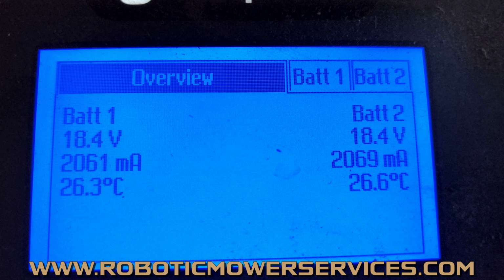That is not completely correct, because if you look at this right here, obviously we're working with a 450 because we got battery 1, battery 2. We got a charge current coming into both the batteries. We have 18.4 volts coming in to both batteries. So we have good voltage coming in, but we have 2061 milliamps coming into one battery, 2069 milliamps coming into the other. We can go up to 7,000 on here. We need a minimum of 5,600. That's our 80% of 7,000.